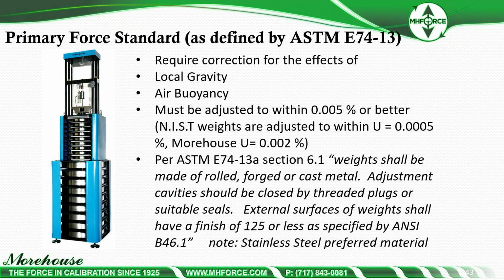NIST is of course the best, but they also have long lead times and they are very expensive. They're about 80 grand for a typical machine just to calibrate weights. So if you have the money and want the best, NIST is the best. But for the typical calibrations, most state labs can even do 10 to 20 parts per million. When we do weights for people, we have them adjusted. Right now we're getting ready to send weights to Mettler, and they'll be adjusted to within 10 parts per million. And weights shall be made of rolled, forged, or cast metal. Typically, we're going to do stainless steel if it's a small weight. It's the preferred material because it does not rust and it is not magnetic.